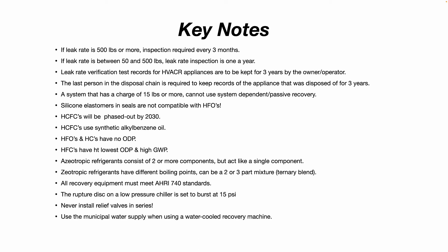Azeotropic refrigerants consist of two or more components but act like a single component across their entire temperature range. They have different boiling points and can be a two- or three-part mixture called a ternary blend. All recovery equipment must meet AHRI 740 standards. The rupture disc on a low-pressure chiller is set to burst at 15 PSI — that's usually a question on the EPA exam. Never install relief valves in series, only in parallel, and they should be piped to the outside of the building.